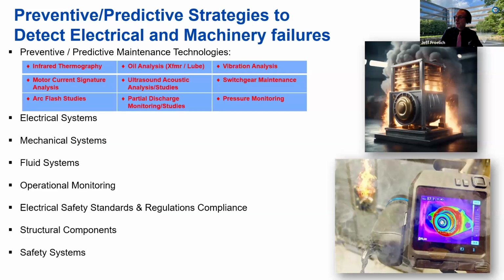Looking at predictive and preventive maintenance strategies, I've listed 9 of them here. There's a host of wide range within the industry, but these are some of the keys: infrared thermography, looking for all kinds of abnormal heat signatures; motor circuit current analysis; arc flash studies; oil analysis for transformers and lubrications, using a 5-part liquid screen, dissolved gas, and oil analysis to check for the condition and health of the oil.